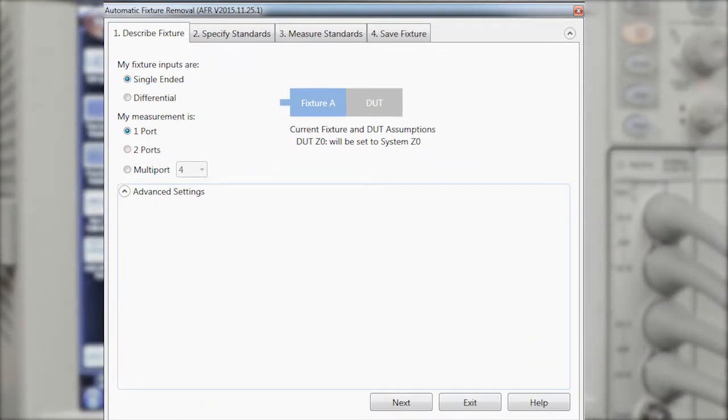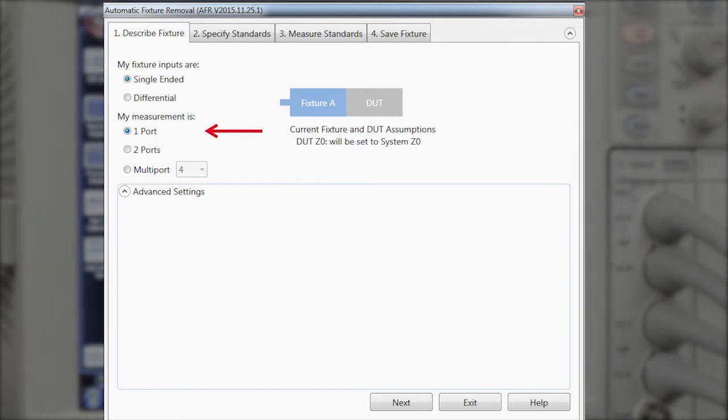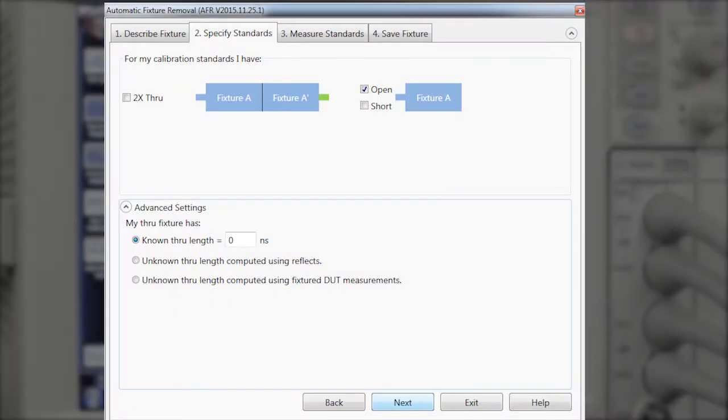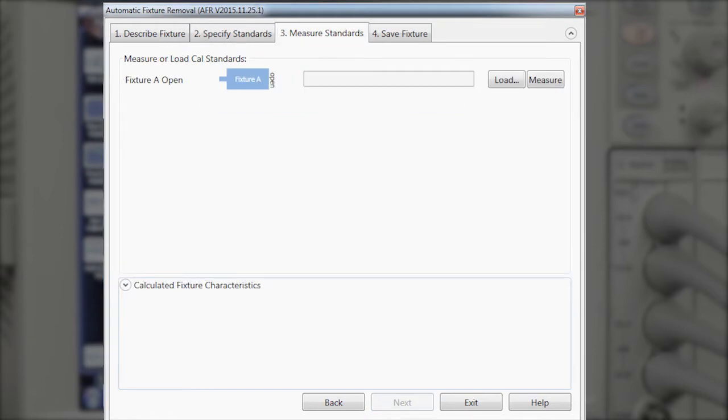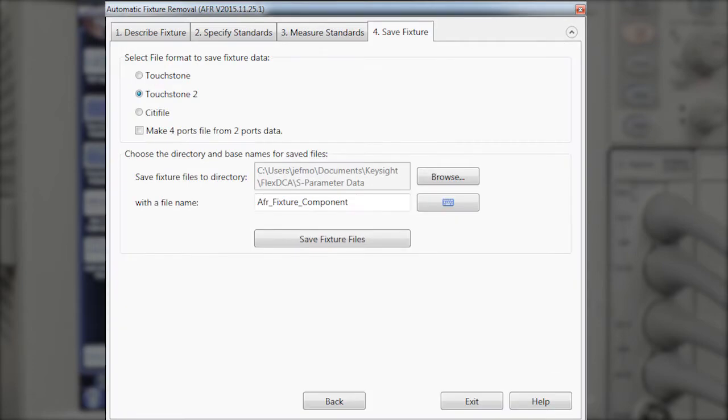This asks us a few questions about the fixture, and it is a single-ended fixture, and we're going to measure one port because you only have access to one port. This lets us tell AFR whether we're going to be measuring an open or a short, and our fixture is open. And finally, it's time to make the measurement. So we click measure, and now we can just save the file.